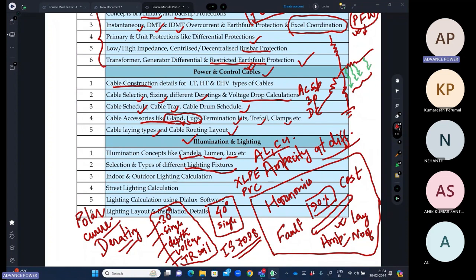Based on that you select the fixture for different areas. For a control room it will be different, supposing it is recess type, batten type, or LED bulb type. We'll see the polar curve and accordingly select the type of fixture. We'll calculate the number of fixtures manually for both indoor and outdoor lighting, and do the same with the help of Dialux software. First we'll prepare a room, or say a switchgear room, then place a chair, table, door, window, everything in there. We'll place a light fixture and do the lux calculation.